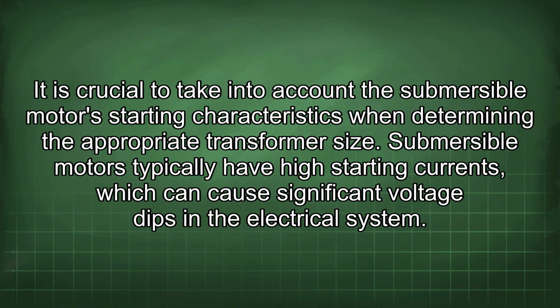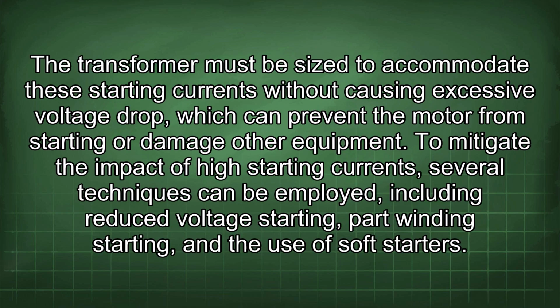It is crucial to take into account the submersible motor's starting characteristics when determining the appropriate transformer size. Submersible motors typically have high starting currents, which can cause significant voltage dips in the electrical system. The transformer must be sized to accommodate these starting currents without causing excessive voltage drop, which can prevent the motor from starting or damage other equipment. To mitigate the impact of high starting currents, several techniques can be employed, including reduced voltage starting, part winding starting, and the use of soft starters.